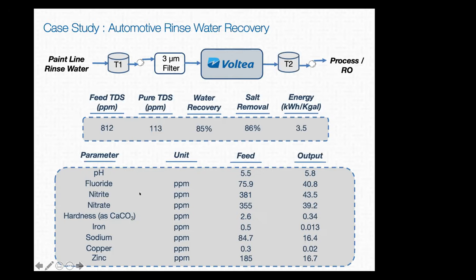You can see here the quality down below. In this case, the hardness was around 2, and we pulled that out. The nitrates were up around 355. We pulled those down to around 40. Sodium, 84, down to 60. Zinc is very high because it's a zinc-based cleaner that they use in a number of these tanks, up around 185, and then dropping that down to 16. So we're dropping a lot of that TDS down to a nice low level, where they can then reuse that water because we've improved the quality, saving them money, saving them costs, saving them water.